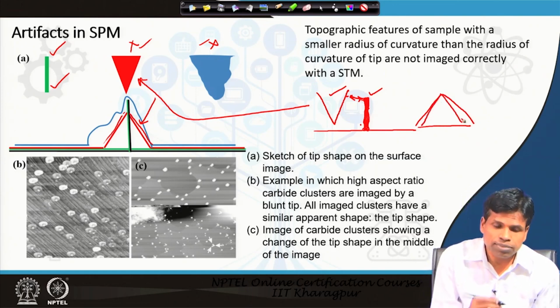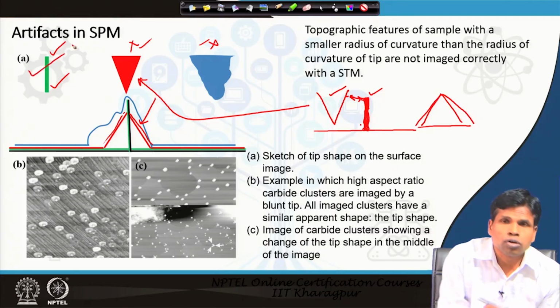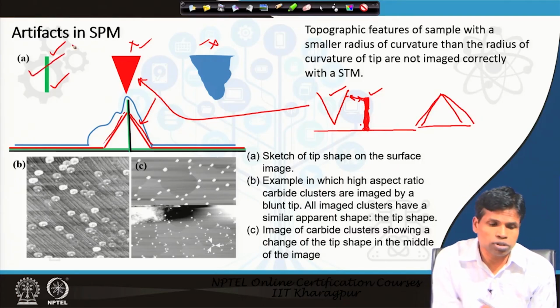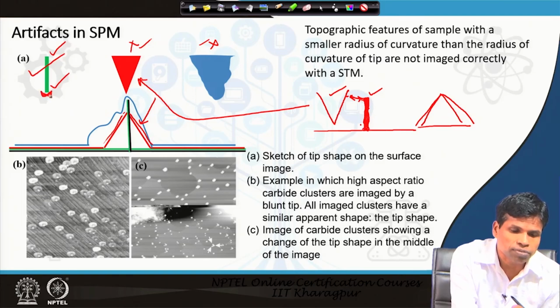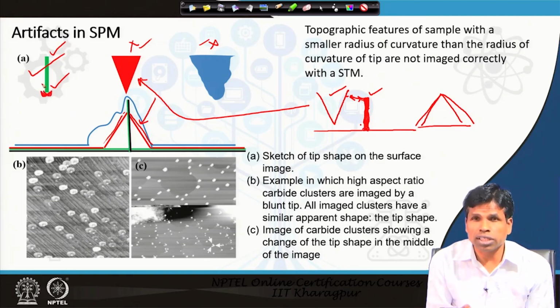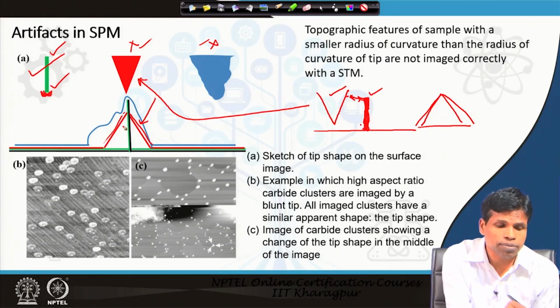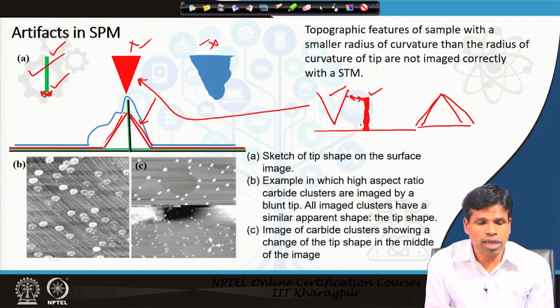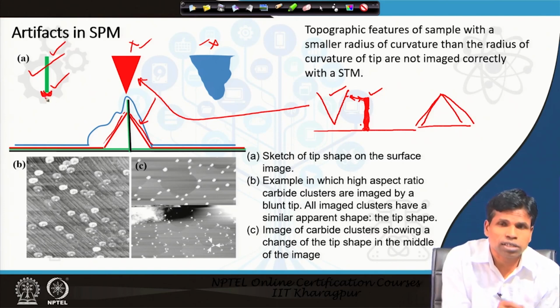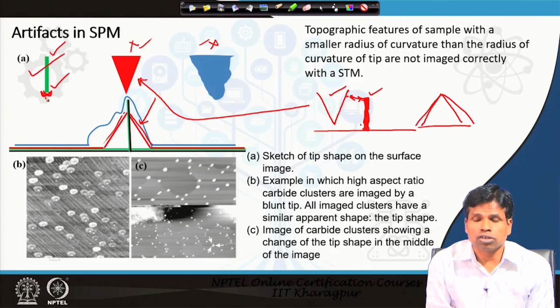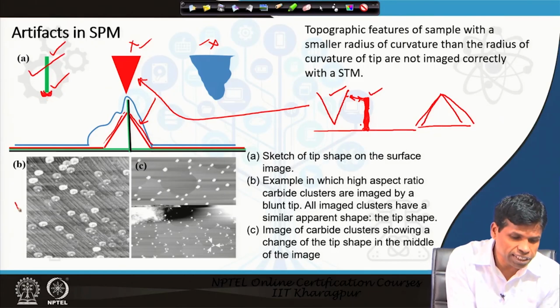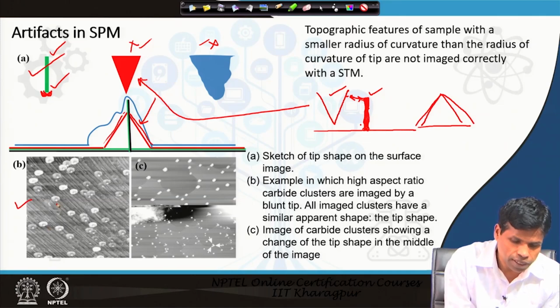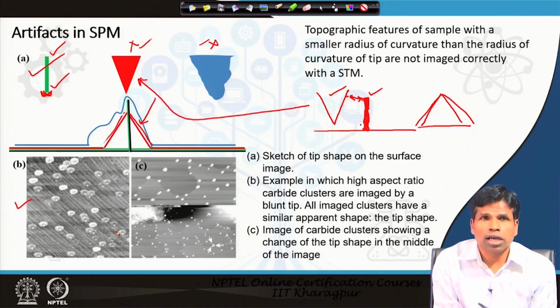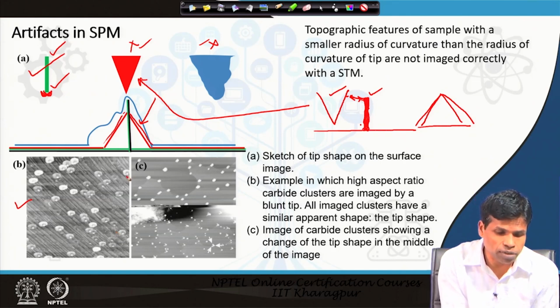So, it is very important to have a tip which is of high aspect ratio. In addition to that, the tip curvature should be smaller than the curvature of the sample. If the tip curvature is larger, then we cannot get the correct image of the sample.